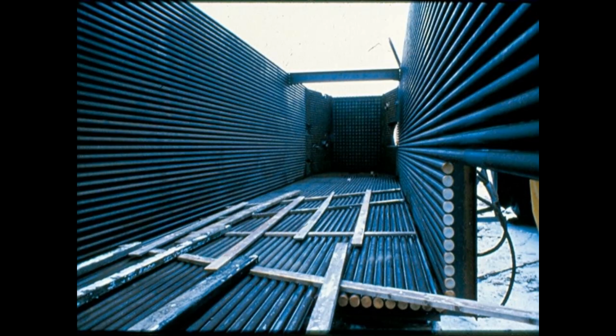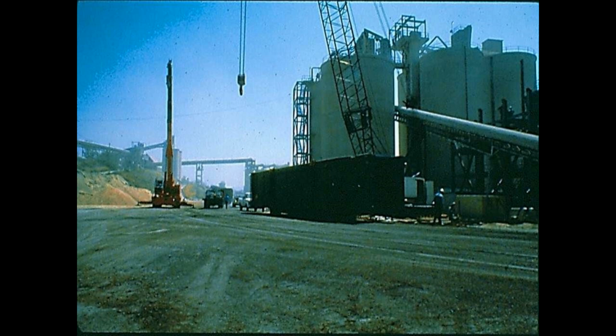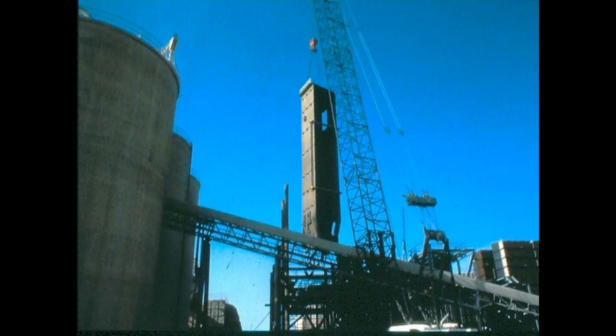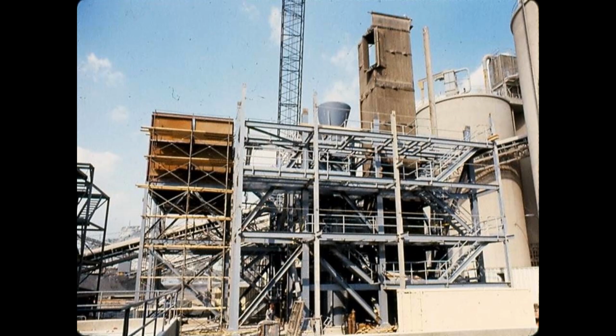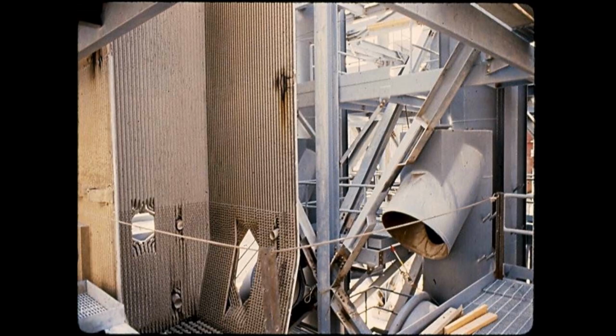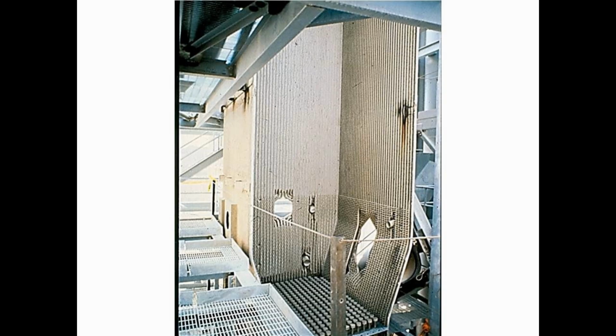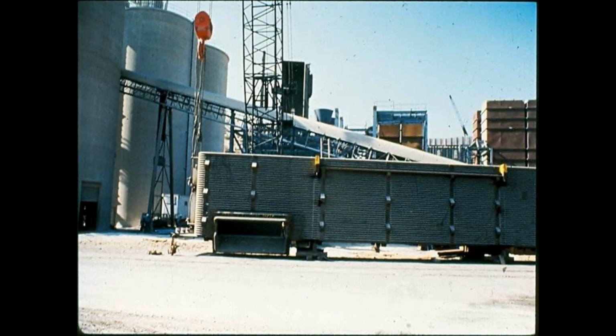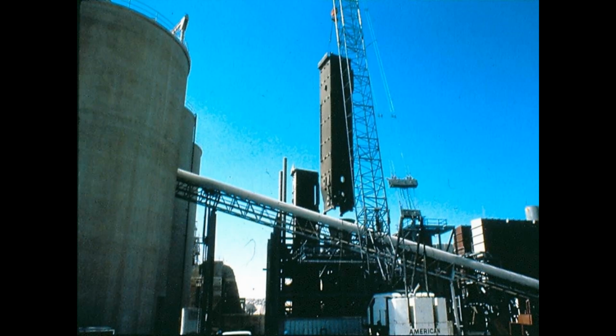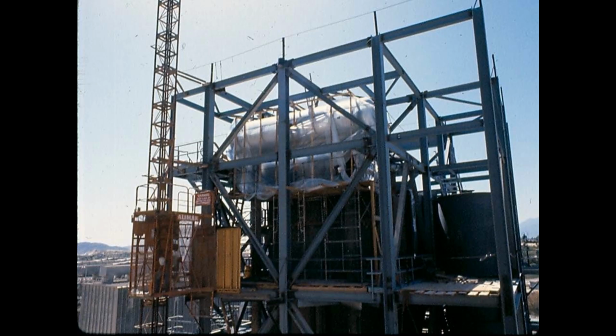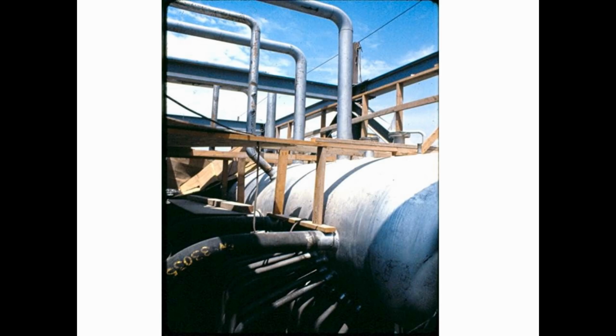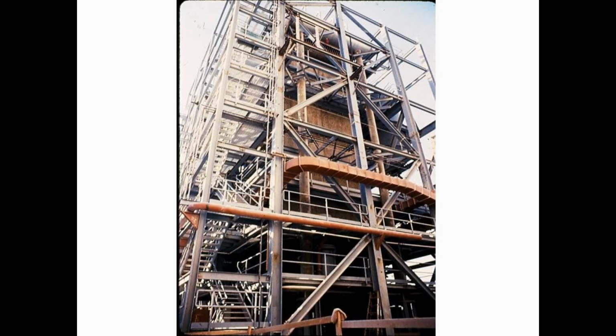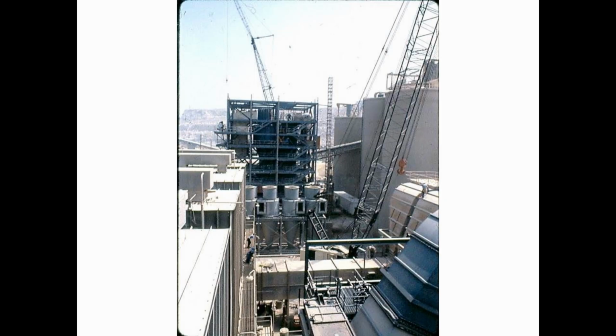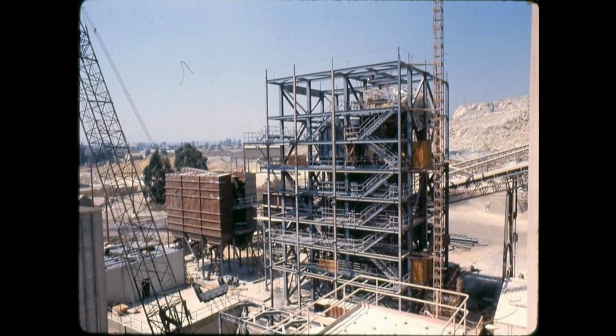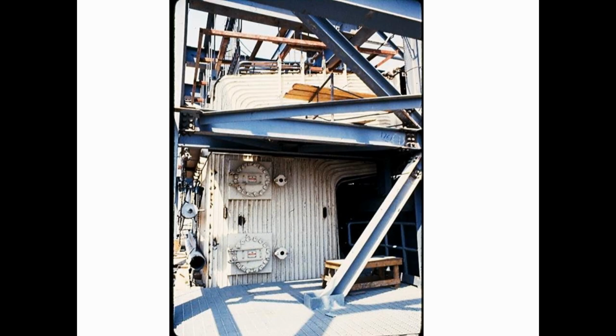Prepared coal is fed from a 4-hour surge hopper to the loop seals by drag link conveyors. Each conveyor has 2 discharge openings located above rotary feed valves which seal against the boiler pressure. Final steam conditions produced by the boiler are 650 psig pressure and 825 degrees Fahrenheit temperature. Steam output from the boiler is 172,000 pounds per hour. The fluidized bed combustion system provides a combustion process which utilizes limestone as an SO2 sorbent.